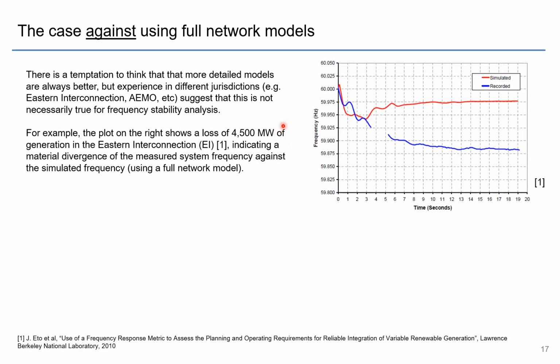So consider this plot here from the Eastern Interconnection in the US, where the red line is a simulated frequency trace for a 4,500 megawatt generator contingency using the full model, and the blue line here is the measured trace. And you can see some real material divergences between the simulated and the measured traces. And the worst thing is that the simulated one is actually far more optimistic than what was actually measured, which was this lazy L frequency response curve.